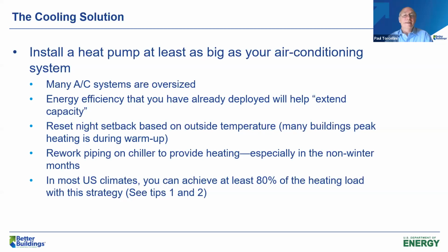Reset the night setback temperature based on the outside temperature—as it gets colder out, use less setback. Many buildings peak their heating system during that warm-up, so you can extend that time or not set back as much, especially when you know it's going to be very cold, to take advantage of downsizing that heat pump system a little and keep it more consistently running.